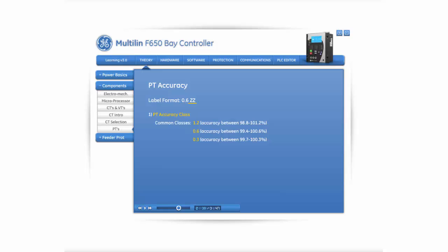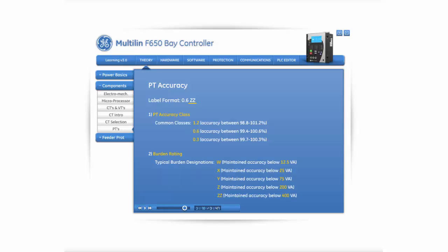The next character in the label is a letter designating the burden rating. The typical burden designations and their corresponding ratings are as follows. The W rating indicates the PT will operate accurately as long as the burden doesn't exceed 12.5 volt amperes. The X rating indicates the PT will operate accurately as long as the burden doesn't exceed 25 volt amperes. The Y rating indicates the PT will operate accurately as long as the burden doesn't exceed 75 volt amperes. The Z rating indicates the PT will operate accurately as long as the burden doesn't exceed 200 volt amperes. And the double Z rating indicates the PT will operate accurately as long as the burden doesn't exceed 400 volt amperes. If at any time the burden exceeds the PT's rating, the accuracy classification will be compromised.